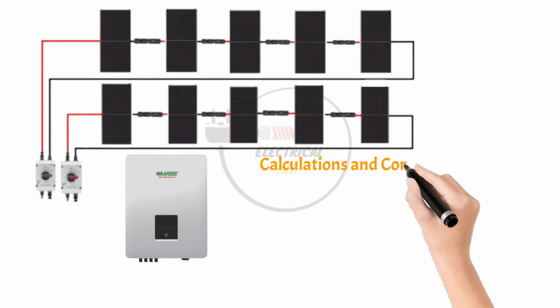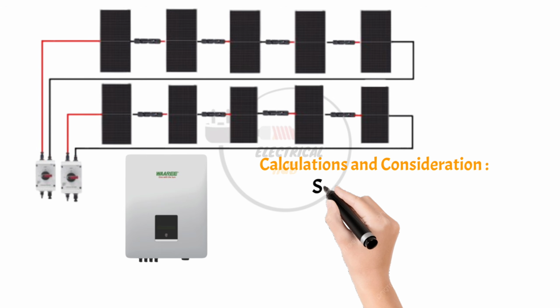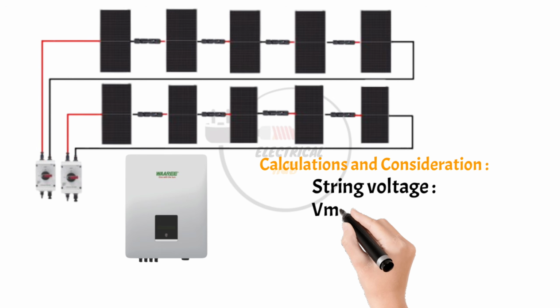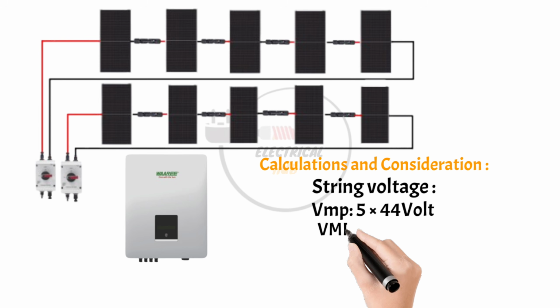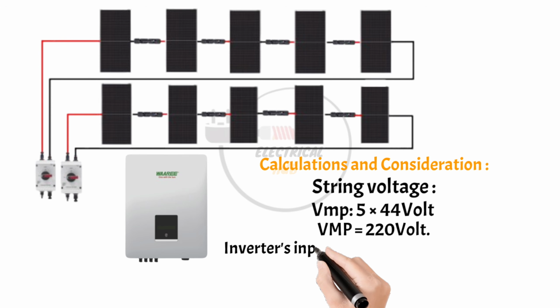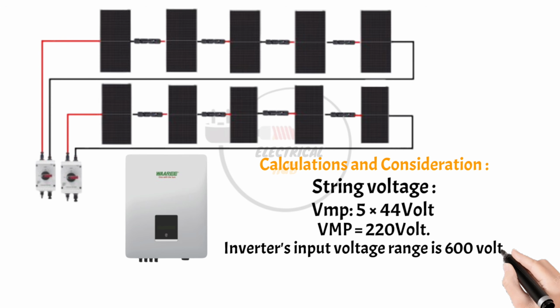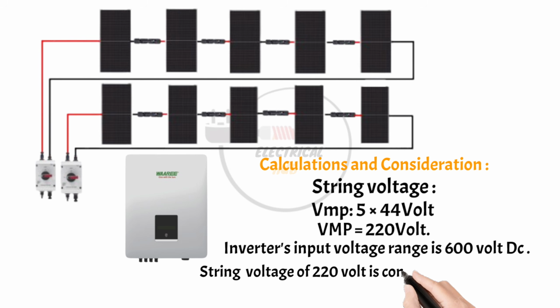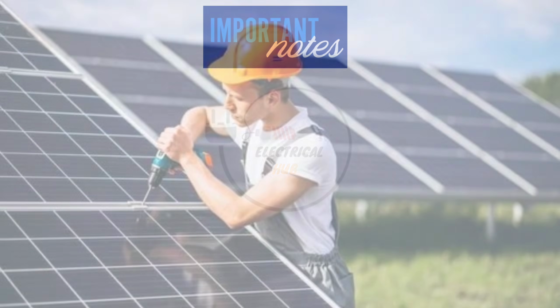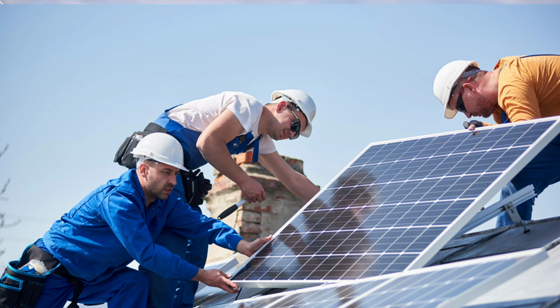Calculations and considerations. String voltage with 5 panels in series. The voltage of each string will be VMP equals 5 multiplied by 44 volt. VMP equals 220 volts. Inverter's input voltage range is 600 DC. String voltage of 220 volt is comfortable in this range. Since the inverter has 2 MPPT trackers and you have 2 strings, each string can be connected to a separate MPPT tracker. This is ideal as it allows the inverter to optimize the power output of each string independently, even if they experience different sunlight conditions. Fifth, important notes. Professional guidance. It is highly recommended to consult with a qualified solar installer.